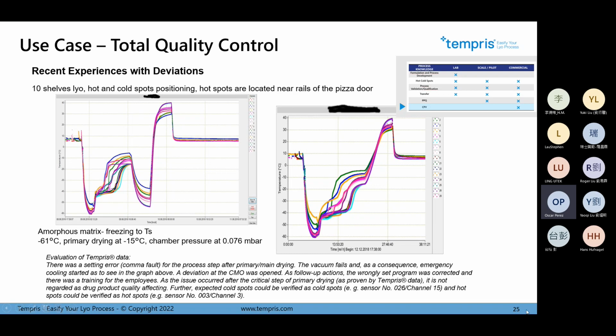This is a normal cycle on the right side, and here in this cycle, which is the same product, the freeze dryer failed, the chamber pressure went up, and then automatically the freezer reacts, freezing the product and going down until the problem was solved. If we have this problem in a freeze dryer, which is a vacuum fail, or another problem could happen that makes a deviation in the behavior of the cycle, we can lose the product.